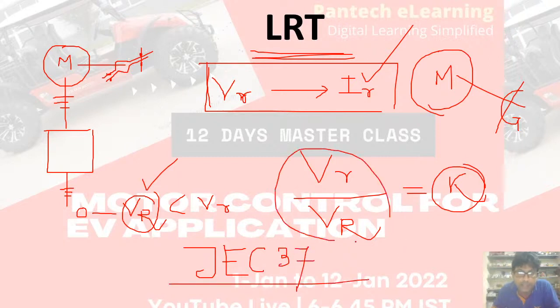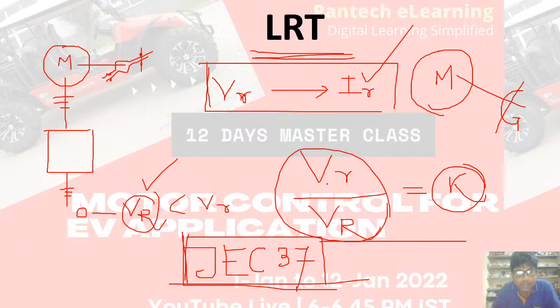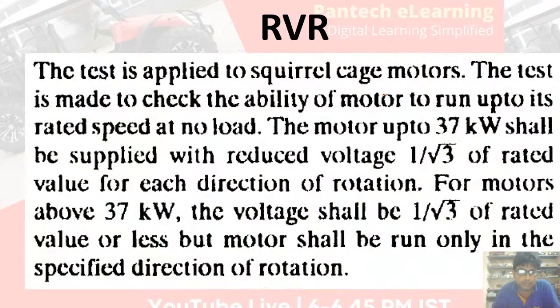Even though I have shown here a linear relationship, actually it is slightly non-linear, and that is clearly elaborated in JEC 37. But as a thumb rule, you can find the inrush current using this method, and for that this locked rotor test is important.